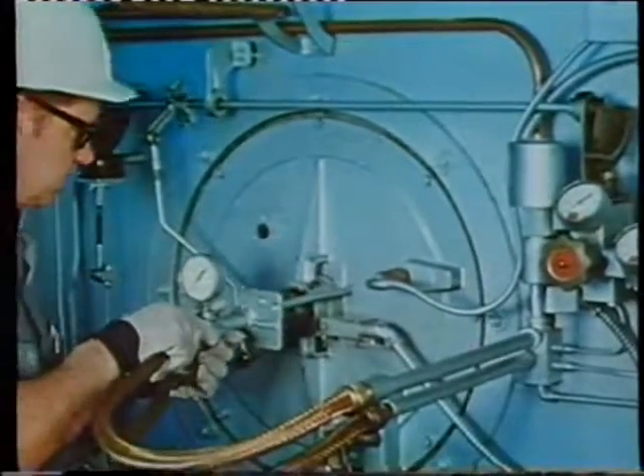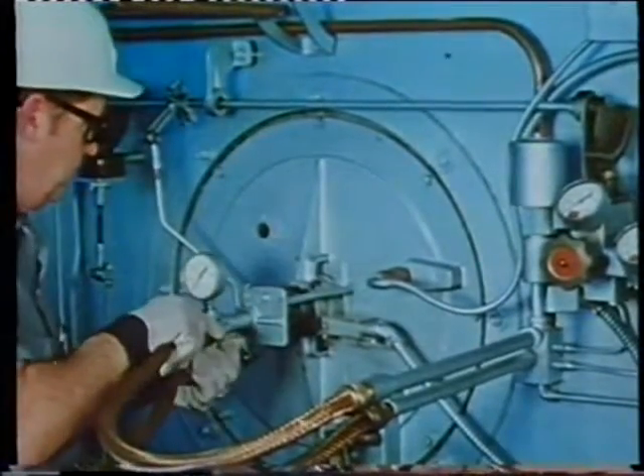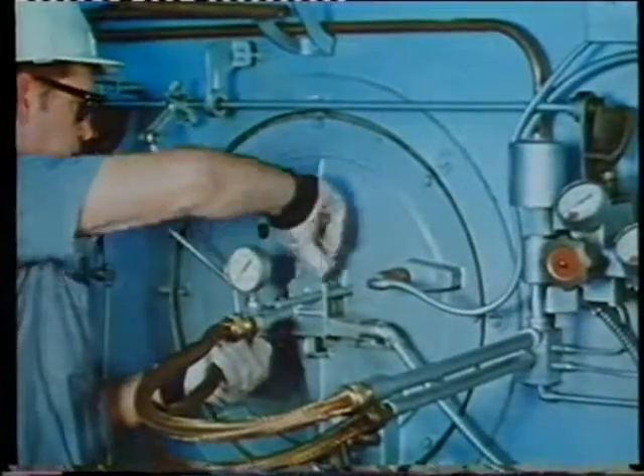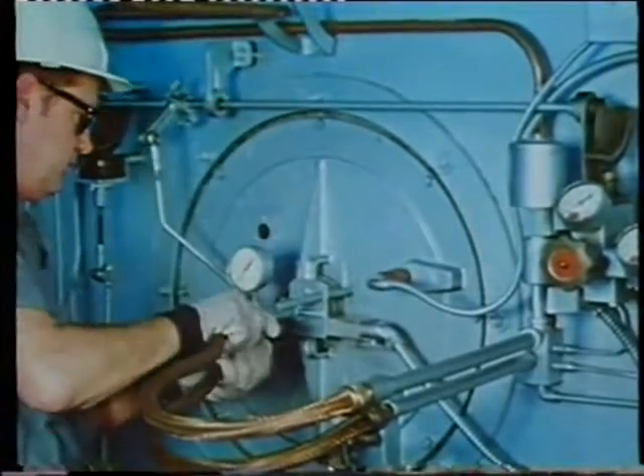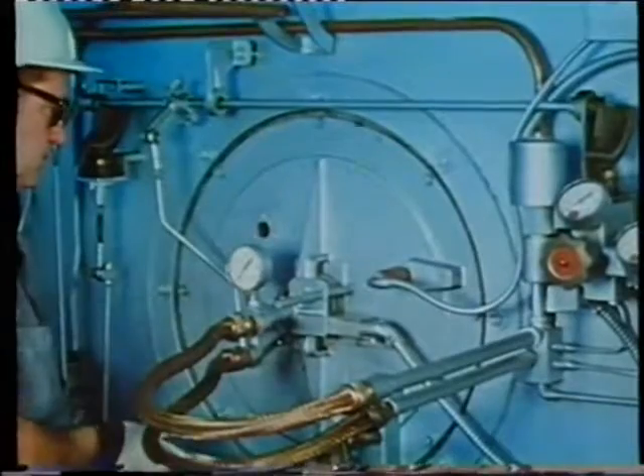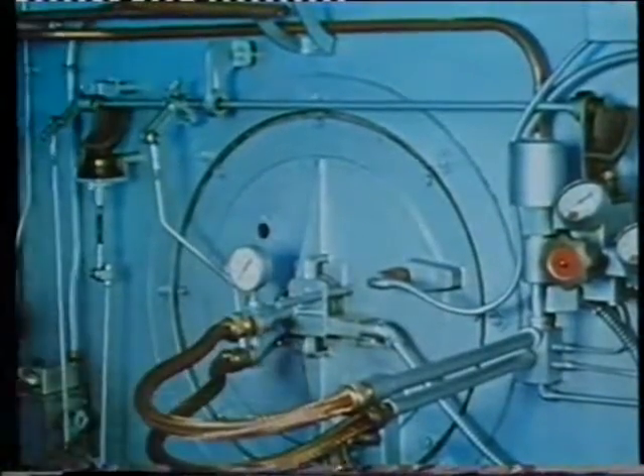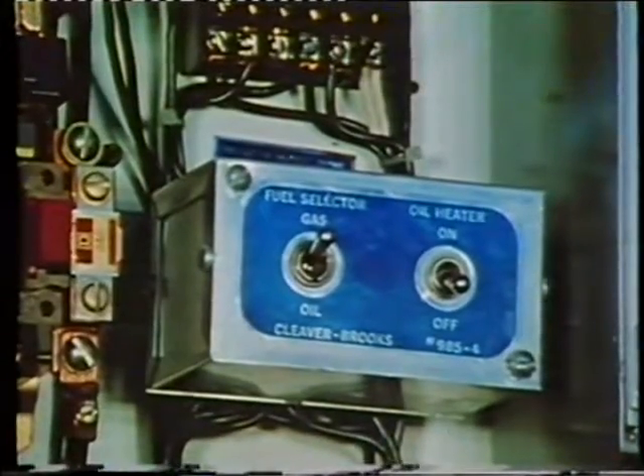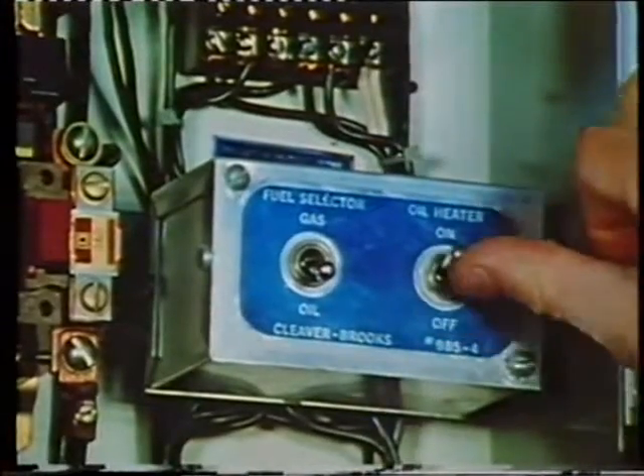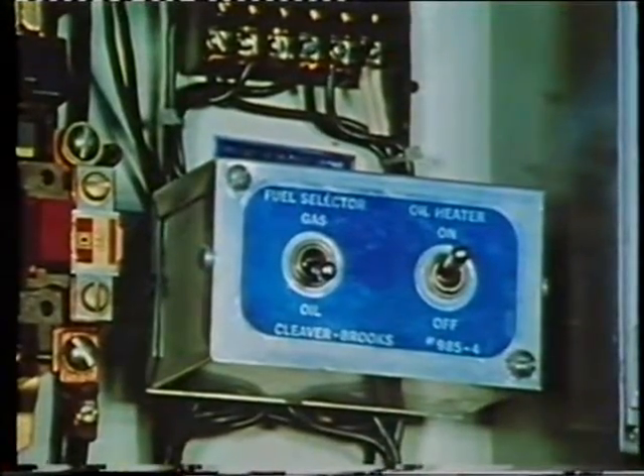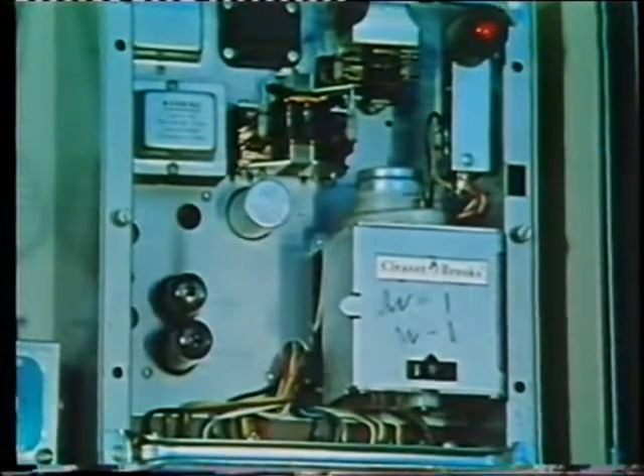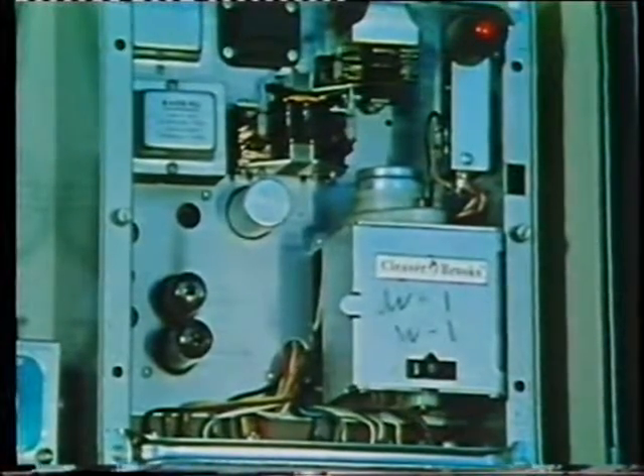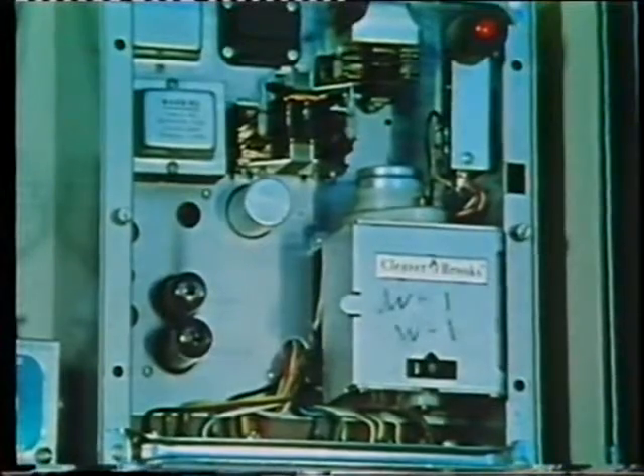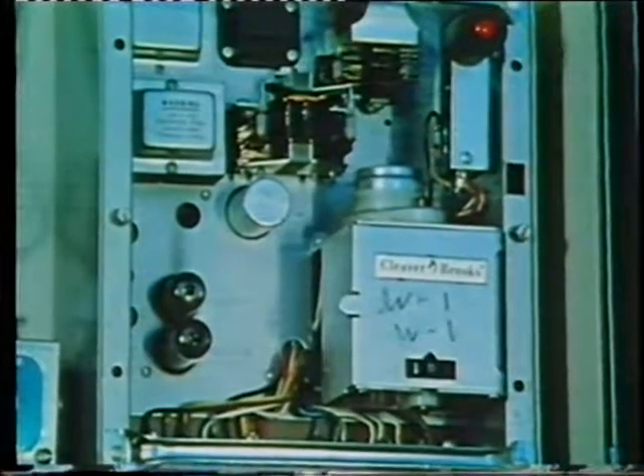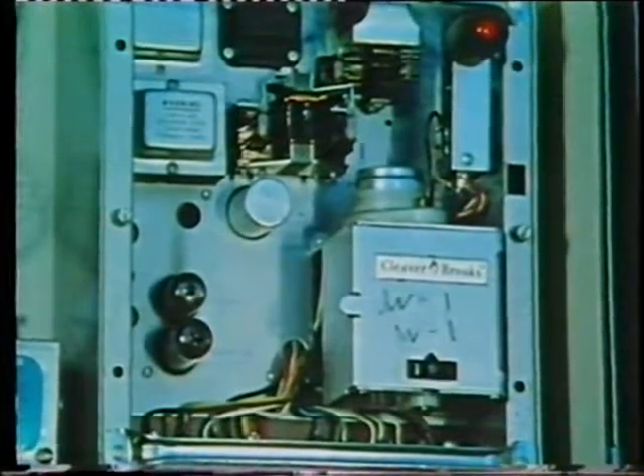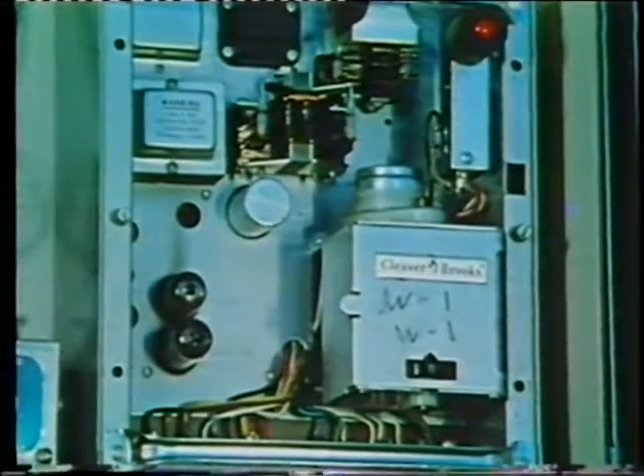In most boilers, the burner unit is readily accessible. To burn oil in a dual fuel boiler, the oil burner assembly must be placed in the burning position. The fuel selector switch is set to oil, and the oil heater switch is turned on. Fuel should now be available when the programmer calls for it. The program controller provides automatic sequencing of the ignition cycle and shuts down the boiler if anything goes wrong during operation.